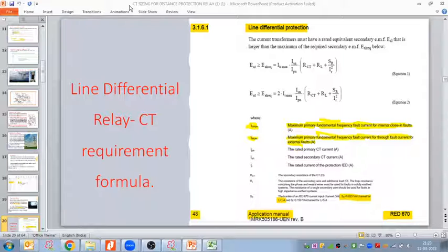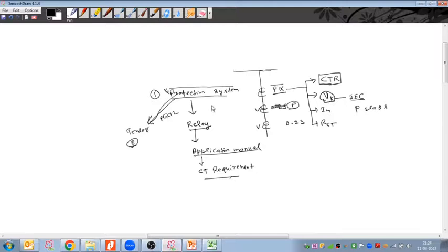I'm telling you, suppose we are doing any kind of solar project in India or anywhere, and the developer doesn't have such protection and control philosophy. In that case, you can follow that country's grid protection and control philosophy, because whatever you are making, solar or wind, you are going to connect with the grid only. So your protection system should be as per the grid protection system. If the developer has not given any specifications for the control and protection requirement, you can refer to the national grid protection system.